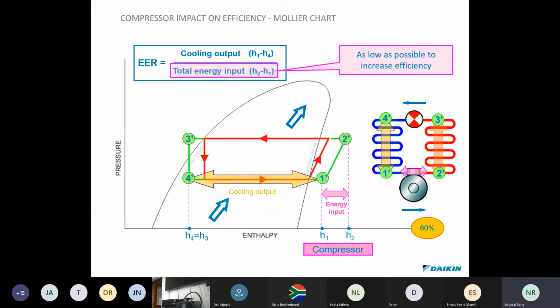So how do you look at EERs? Look at EER as the cooling output, which is H1 to H4, right? That's that portion there. That's the cooling output, divided by the total energy input. That is your energy input, that is your work done. And the lower the work from H1 to H2, the higher your EER is going to be, because it's obviously divided by that number. So let's say, for example, your cooling output was 3 and your total energy input was 1, you would have an EER of 3.